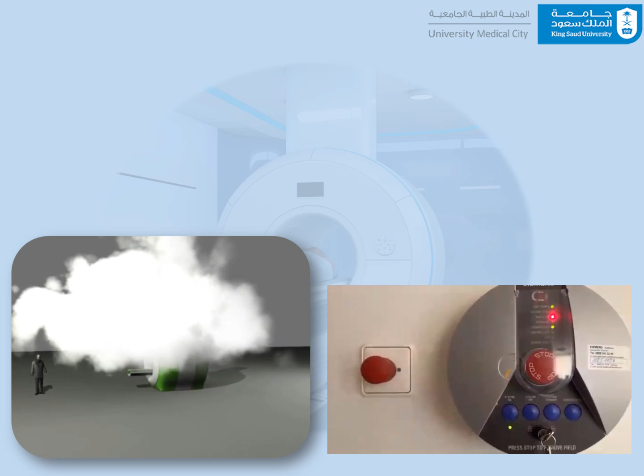When the magnet is quenched, the superconducting electromagnet loses its ability to maintain the strong magnetic field. This causes the stored helium coolant to rapidly escape through the quench pipe, making a loud noise in the process. In the event that the quench pipe fails, the helium can then enter the examination room itself. If this occurs, all personnel in the room should exit the area as soon as possible.